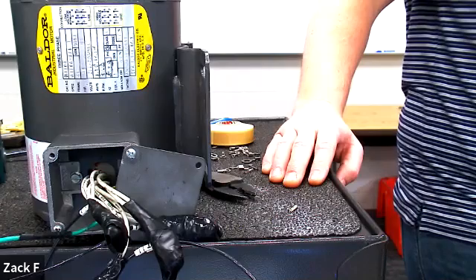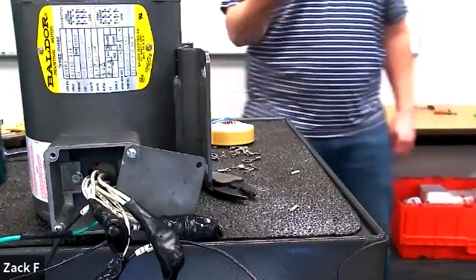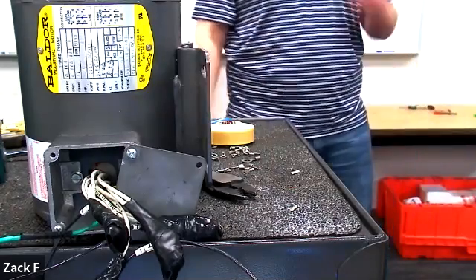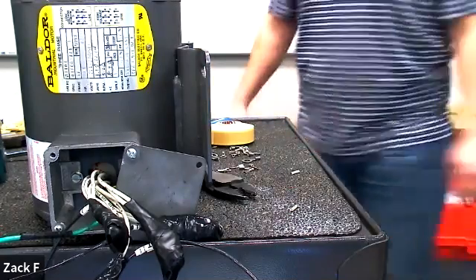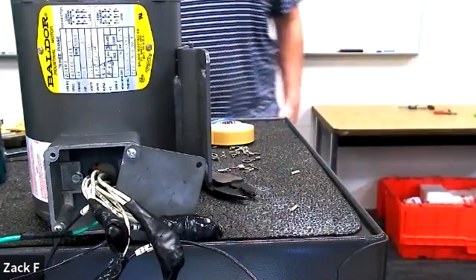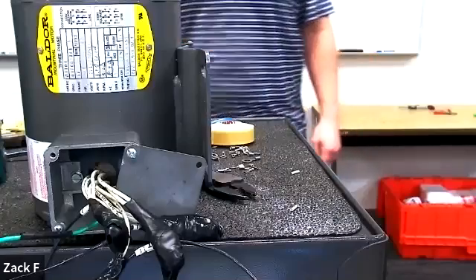I see you guys do it all the time, just checking the ground even after they've checked everything okay with a meter. Yeah. Problem is, sometimes your meter ain't gonna pick up leakage to ground. That's what the megger is for.